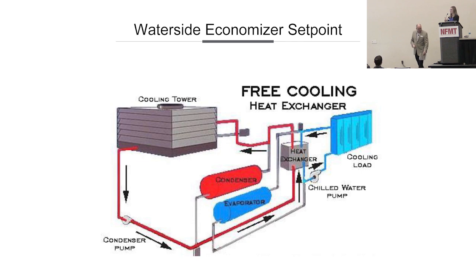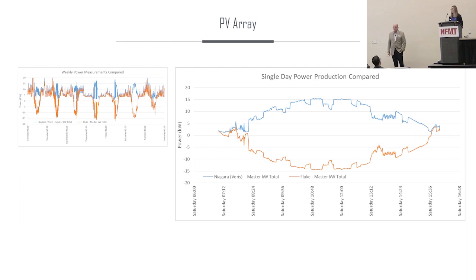One more thing with cooling towers: if you have multiple cells and your turn down ratio is pretty decent, try not to ramp up the fan in one cell and then bring on the other cells. It's more efficient if you run all fans at the same lower speed rather than one fan at a higher speed. You just save energy, back to the fan laws. Yep, back to the fan laws.